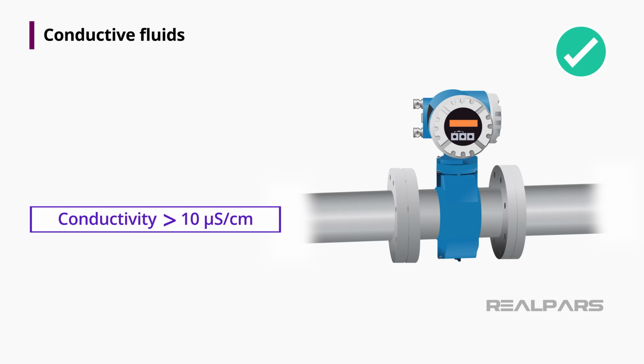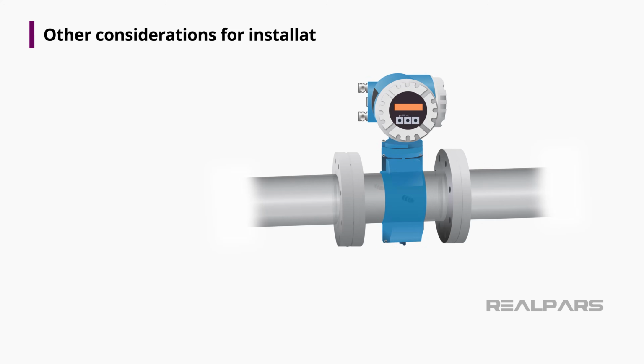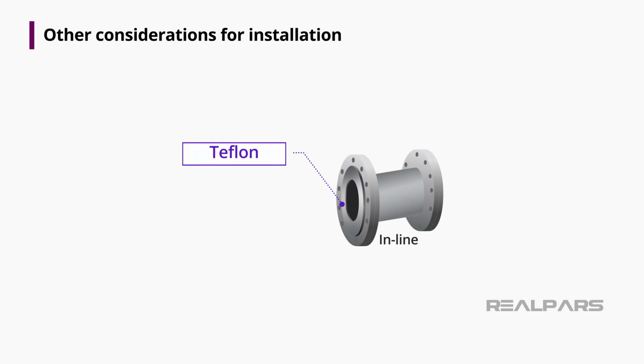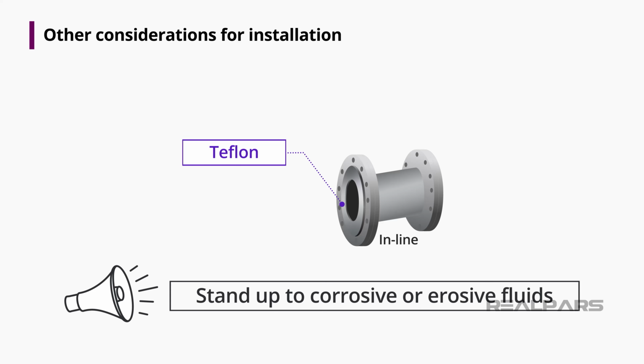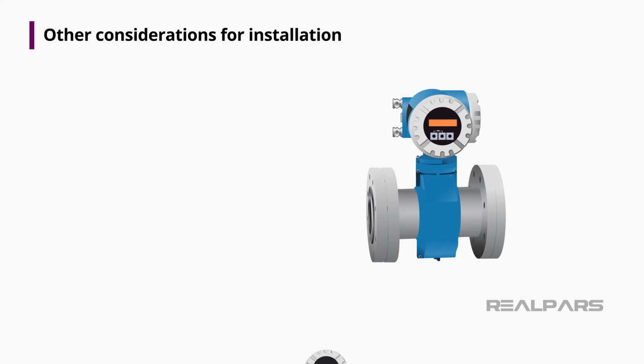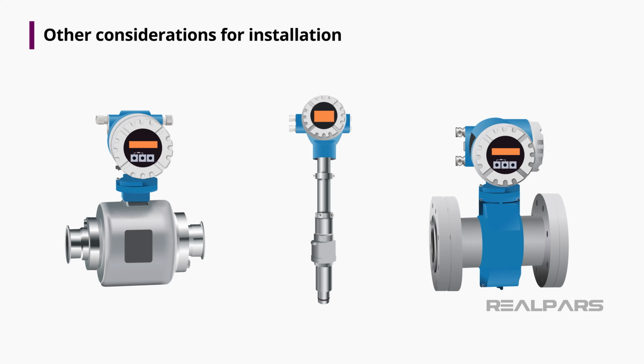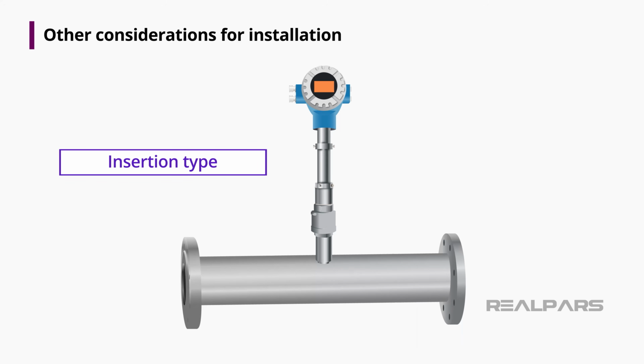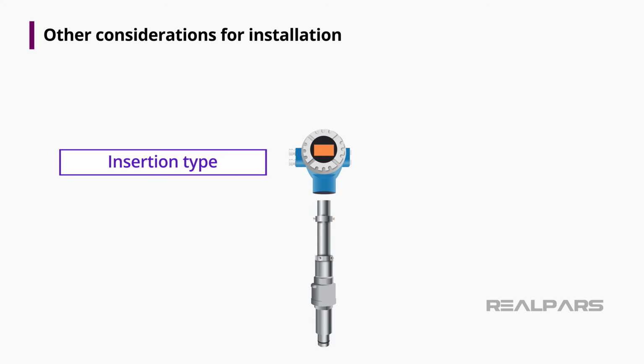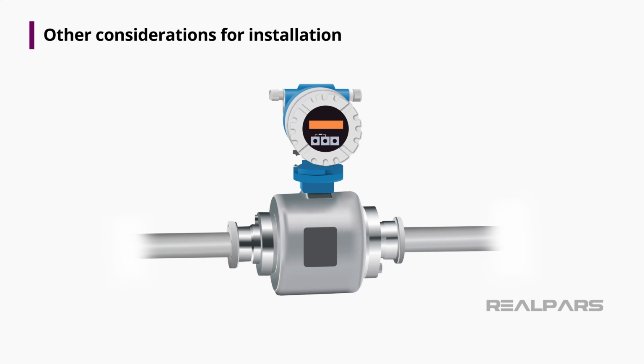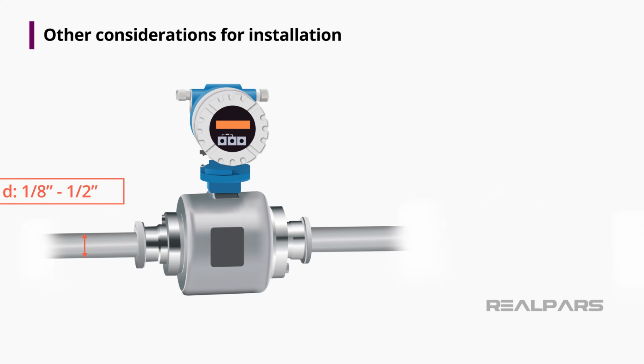In addition to being able to measure a wide range of fluids, inline magnetic flow meters can be lined with Teflon or other materials to stand up to corrosive or erosive fluids, like slurries and acids. There are other types of magnetic flow meters that can be used, including insertion type, typically used with larger pipe sizes, and low-flow magnetic flow meters, which are typically 1/8 of an inch to 1/2 of an inch in diameter.